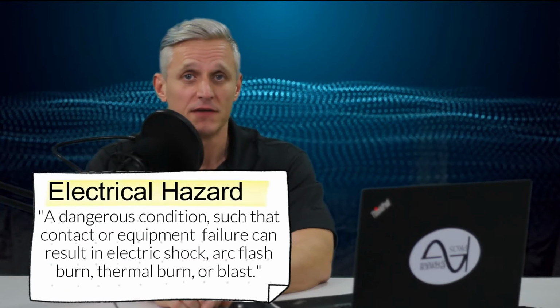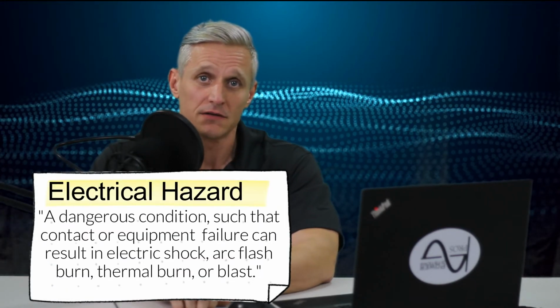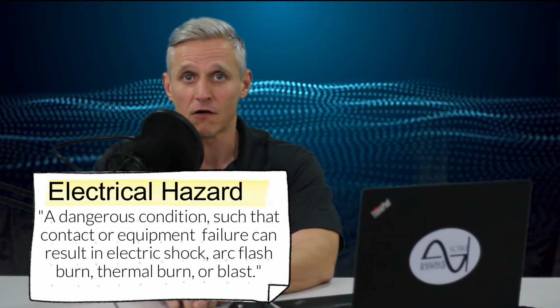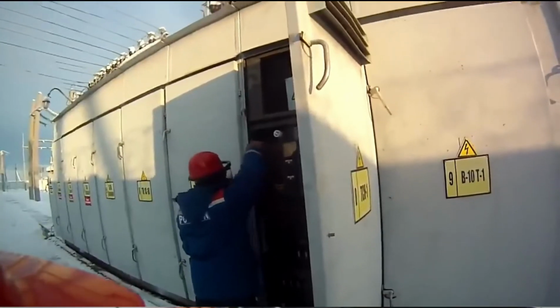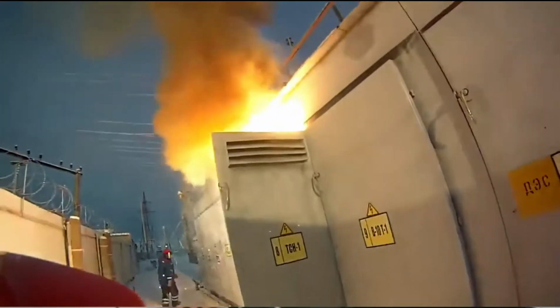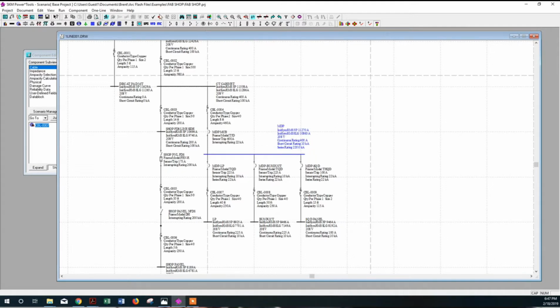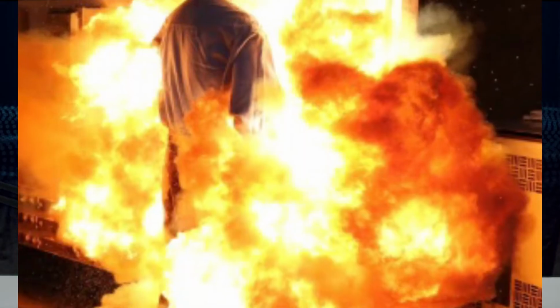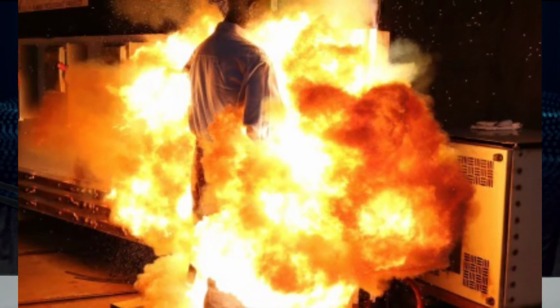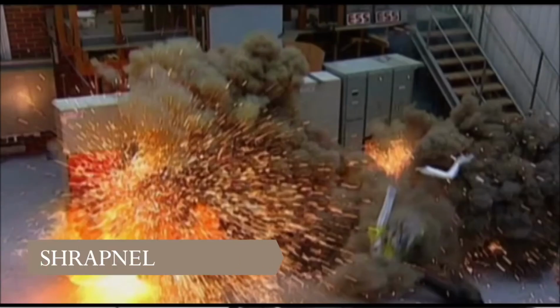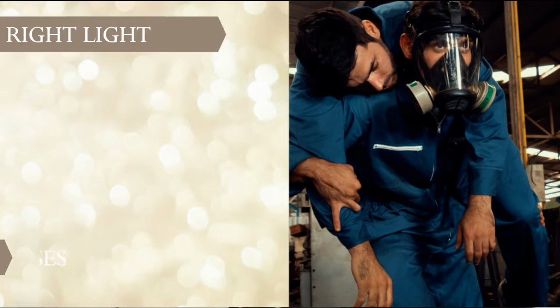An electrical hazard is defined by NFPA 70E as a dangerous condition such that contact or equipment failure can result in electric shock, arc flash burn, thermal burn, or blast. When an arc flash occurs, there are a multitude of hazards that can occur as well. When an arc flash study is performed, the resulting incident energy in calories per centimeter squared is calculated using sophisticated electrical engineering software. However, it only provides information regarding the thermal hazard, which is the amount of heat generated, and using these results only provides the employer with required PPE for the thermal hazard alone. Other hazards involved in the incident can include extreme sound, shrapnel from equipment, molten metal, bright light, and poisonous gases, and we're going to talk about those right now.